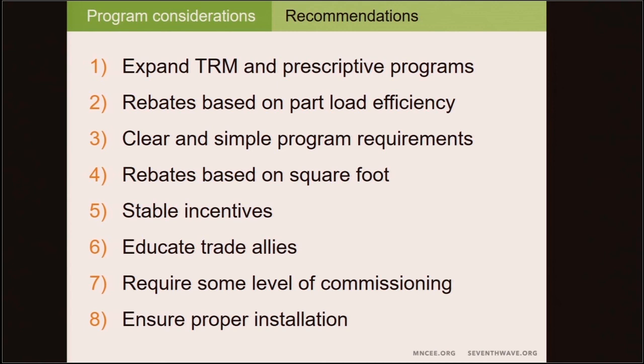Some other additional insights we gathered from our interviews with stakeholders include recasting rebates in units that are more understandable. Prescriptive rebates have traditionally been based on RTU cooling capacity, such as $75 per ton. This aligns well with the energy savings, which scale with cooling capacity. However, it is not a metric that most building owners understand. Potentially recasting rebates based on square foot would make the rebates more understandable from a program participant perspective. It can also be more readily incorporated into project budgeting as it sends a consistent upfront signal.